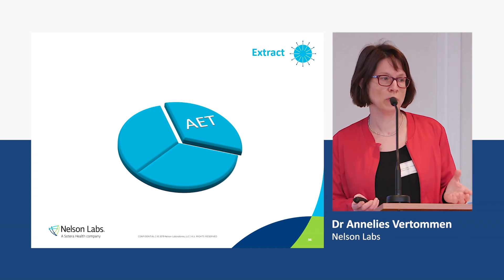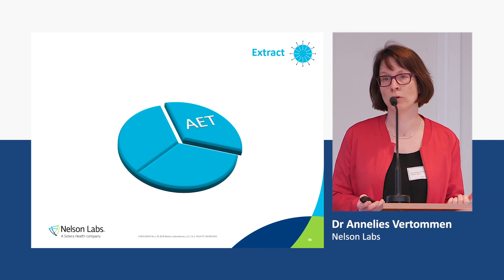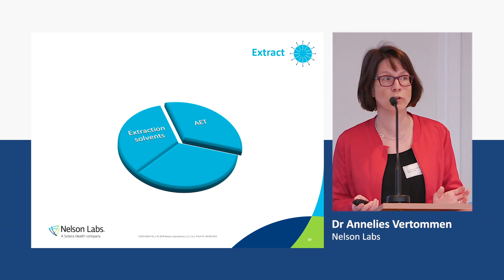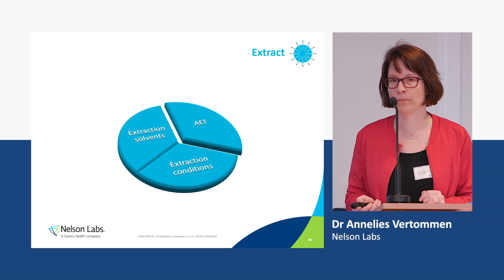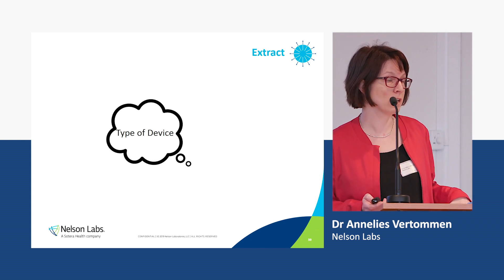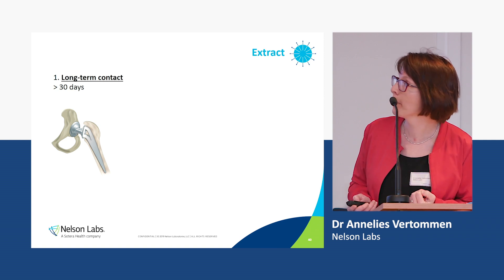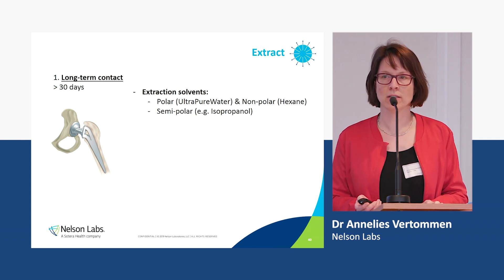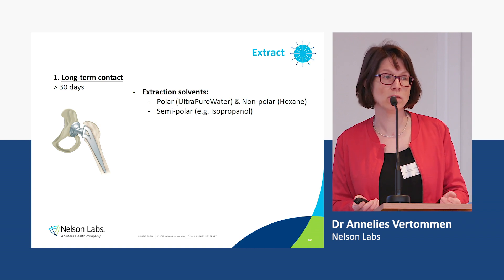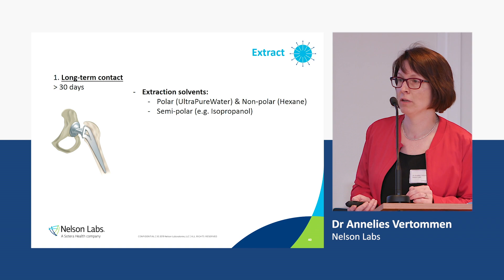You apply this and get your final analytical evaluation threshold to use in your analysis — you divide by the uncertainty factor. Before setting up your extraction study, you need to know this final AET, as it determines the number of devices you'll use and the technically feasible extraction ratio. Other parameters include extraction solvents and extraction conditions. For devices with long-term contact with the human body, the new 18 recommends using at least two solvents — a polar and a non-polar solvent — and, depending on the tissue the device contacts, a third solvent. For blood-contacting devices, it's recommended to also use a semi-polar solvent.